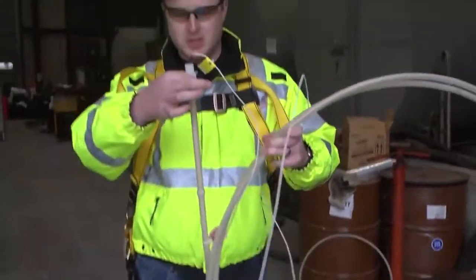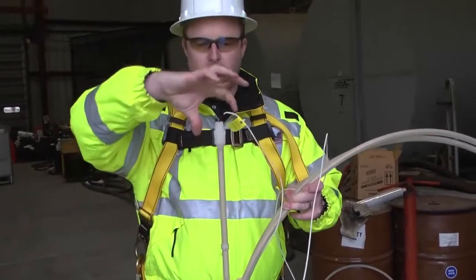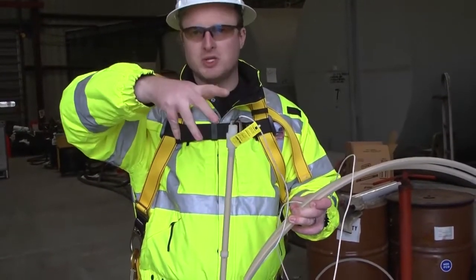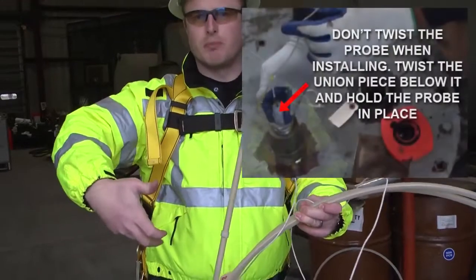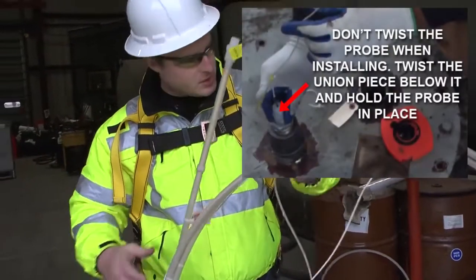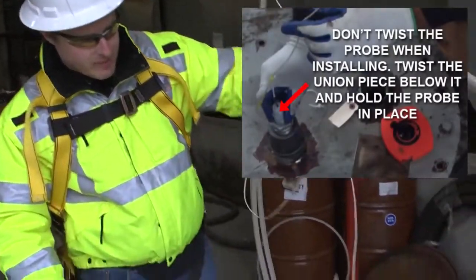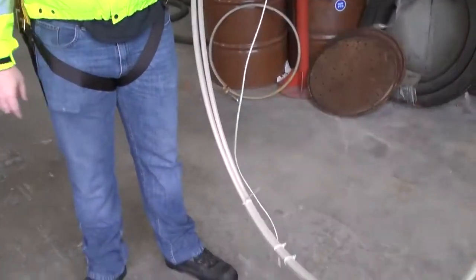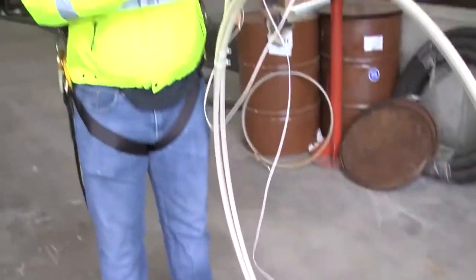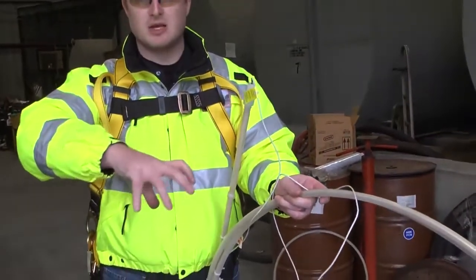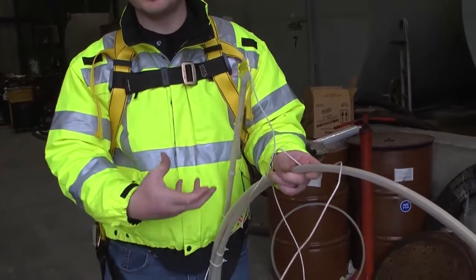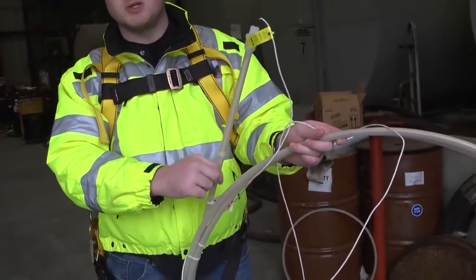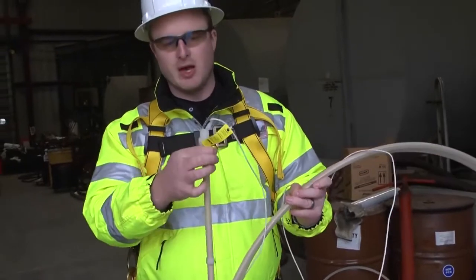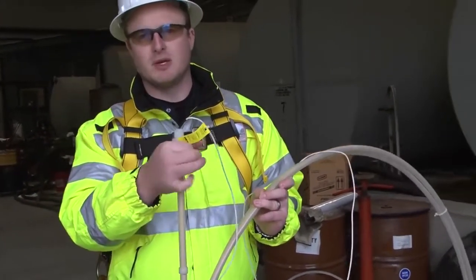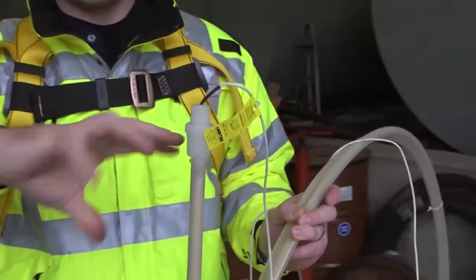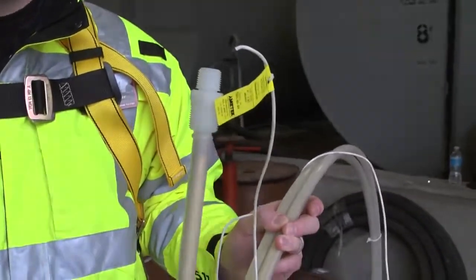And when you go and install it in the tank, the one thing I've noticed a lot when installers will put these in is they'll put this in and then they'll have the cap on top here and they try twisting it, and it's twisting the entire probe in the tank. And remember, when this is in the tank and you have your section down here, you have some pretty heavy weights on it. So what's going to happen is the weights are going to hold that section of the probe, and they're going to be twisting the entire shaft, and it'll cause this electronics piece to break. So you want to make sure you have some sort of union piece up top here so you aren't twisting the entire probe when you're trying to tighten it up in the tank.